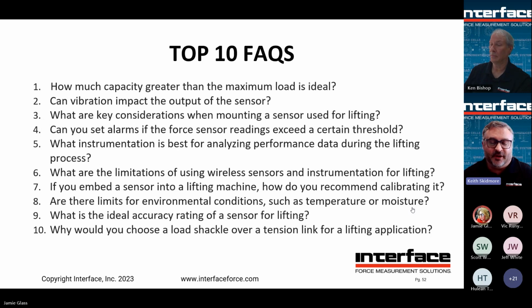Number 7, if you embed a sensor into a lifting machine, how do you recommend calibrating it? Well, it depends, but in most cases, calibrating the entire system makes the most sense. It's the most accurate and takes into account all of the components in the system. Whereas if you just calibrate a load cell by itself, you're not really sure how it interacts with the rest of the components in the system. So ideally, with a lifting device, you'd lift something of a known weight, and that would tell you if it's operating correctly, and then you can actually use that known weight to adjust and calibrate the instrumentation.